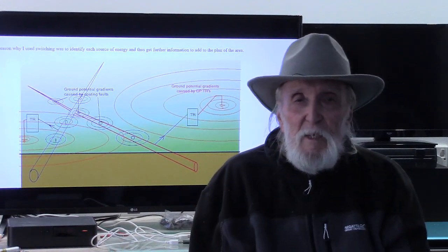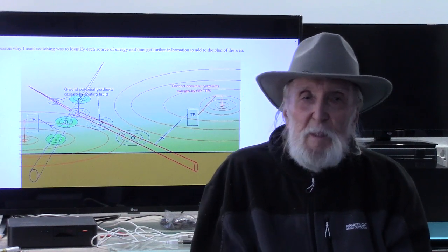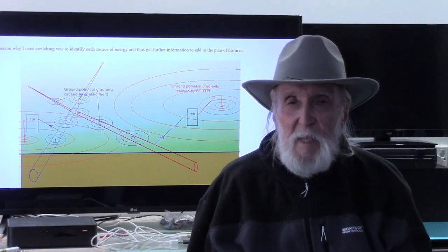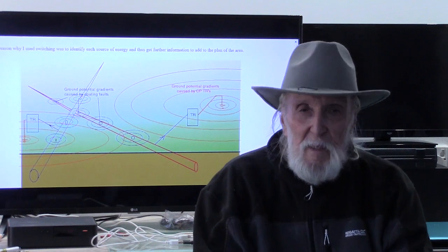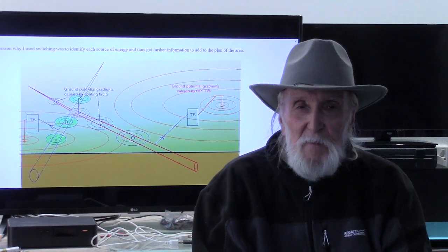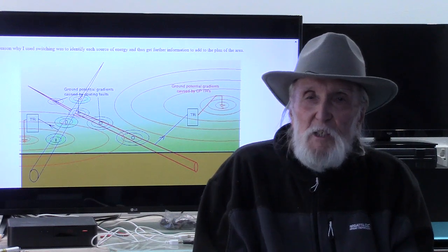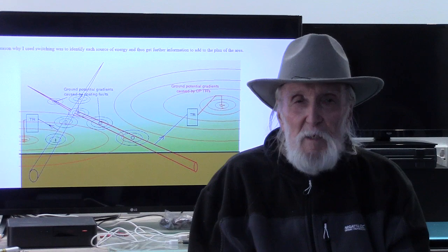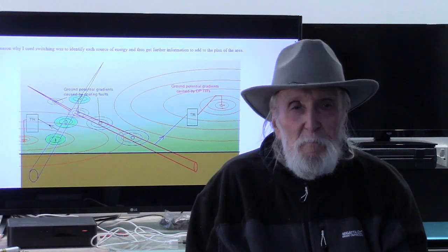It follows that a grounded area of 5 volts or more would be deep green, and that any metal in this area would be protected by the current tending to enter at every interface. This metal would then be charged to an equal voltage to the part of the ground bed profile through which it passed.